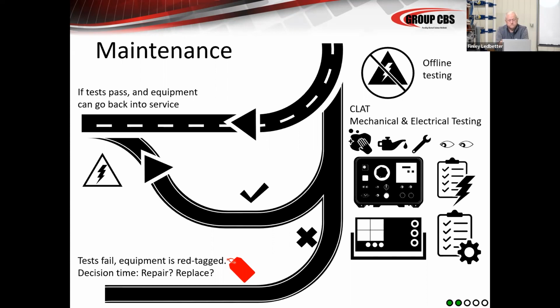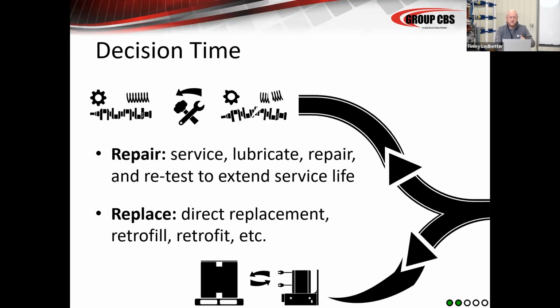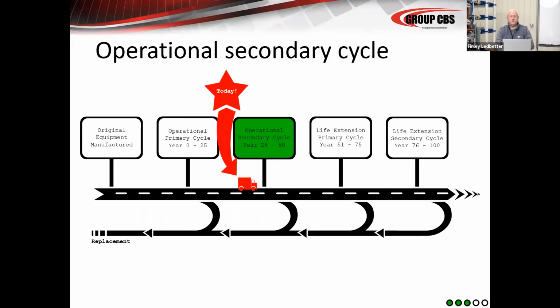Now, every time it goes back onto the racetrack and does 5 more years, it comes back around, and after the first 25 years, it's then decision time. Do I do any mechanical maintenance? Do I do any repair? What do I do? Do I do any replacement? It's been in service 25 years. After 25 years, its original manufacturer's specified life cycle is there, but the equipment's in fine shape. It can be just like new. It can be used many more years, even though it's 25 years old.